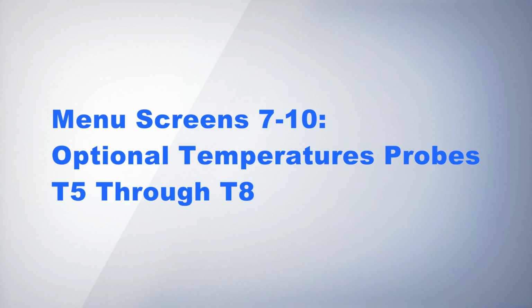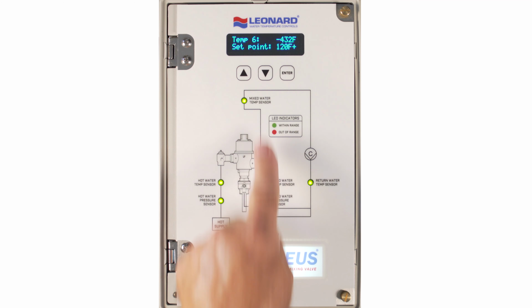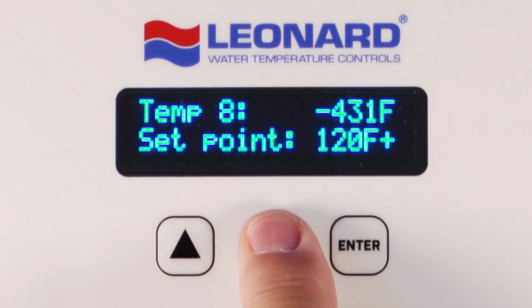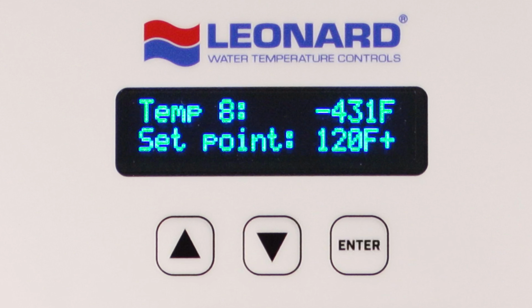Menu screens 7 to 10. Optional temperature probes, T5 through T8. Pressing down between 7 to 10 times displays Temp, 5 to 8, F or C. This indicates and displays actual temperature as measured on RTD, T5 through T8, if the Nucleus is so equipped with the optional temperature sensors. Note: a large negative value displayed is an indication that there is no sensor installed to the daughter board, or the wiring to the main board is improper, or the sensor is damaged.